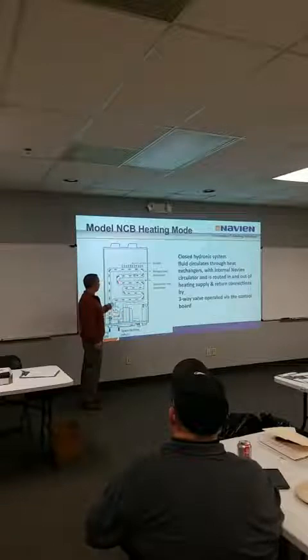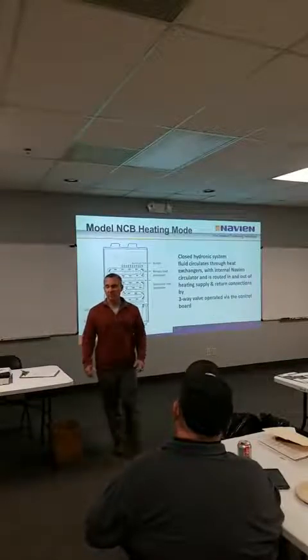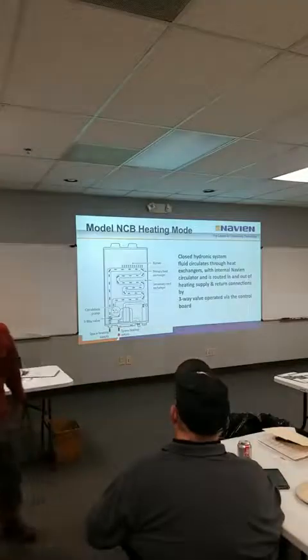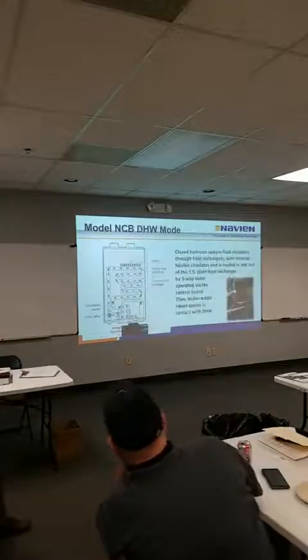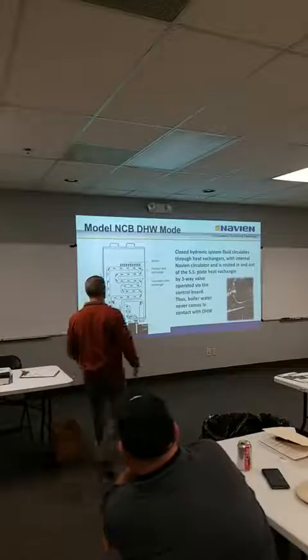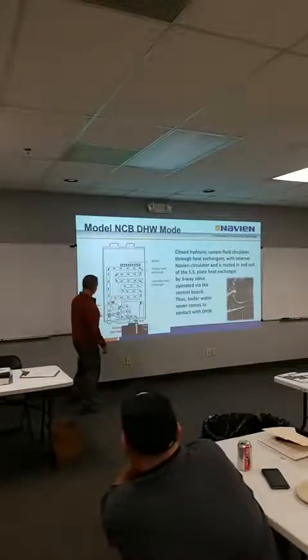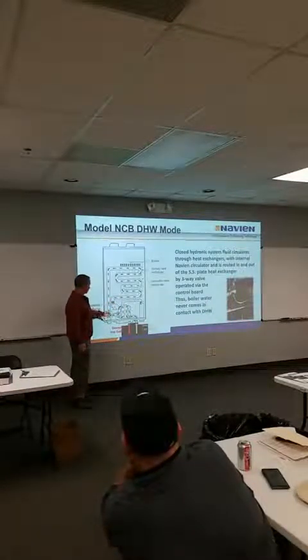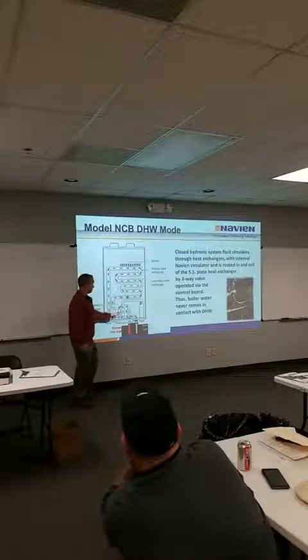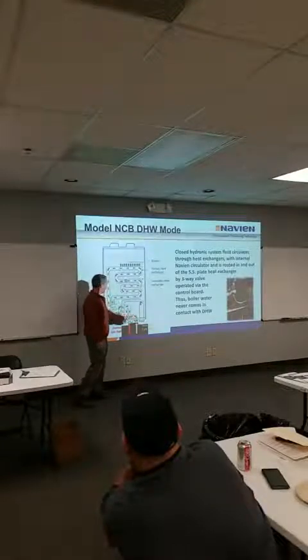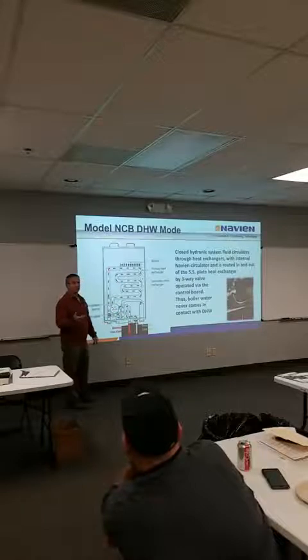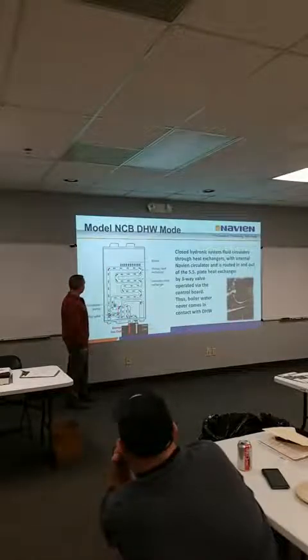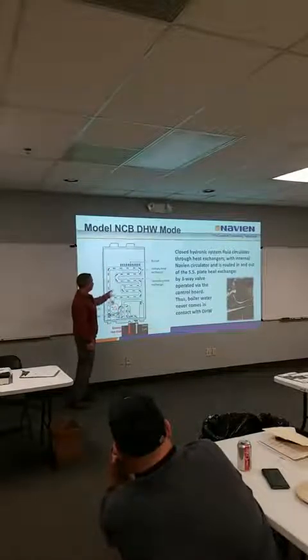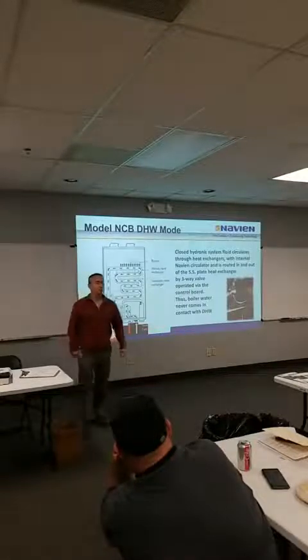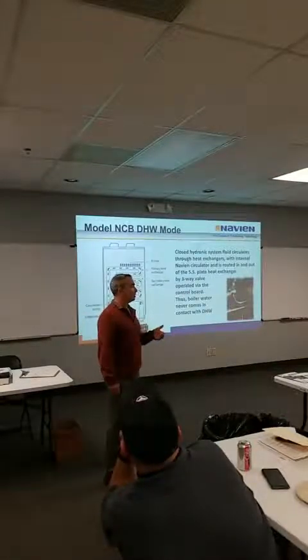So your boiler path, we're using the whole system, sending it out to the field. Again, we have a manifold piped primary, secondary. When we go to domestic on this, somebody turns on a faucet, this 3-way valve rotates, and now we're sending water to that flat plate. So you've got domestic water coming in through the flat plate and out, a very quick path. There's just a flow sensor and some other stuff in there. And we're pumping water through the boiler side. So you will see higher temperatures on your boiler.